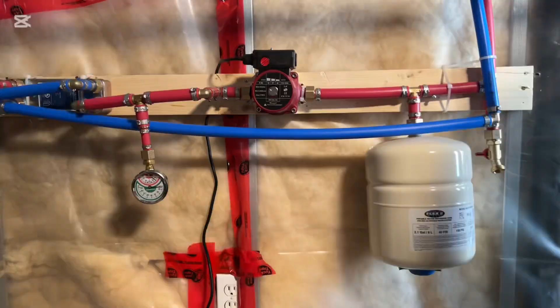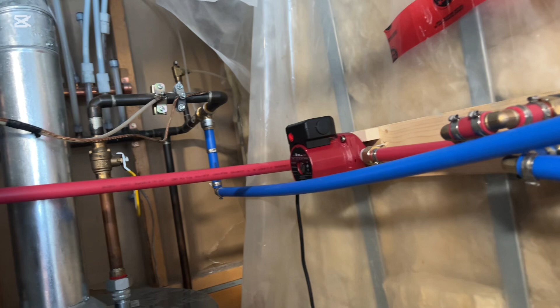Here's the final installation inside the house. I used 3/4 inch PEX, red for the hot side, blue for the return, and just used some 3/4 inch pinch crimp clamps, which work pretty good. The connections to the hot water tank were slightly different, as I used push shark bites there, just because I'm not super comfortable soldering in an enclosed space like that, with pipes that have water in them—it never turns out great. So those shark bite connectors work really good for that.